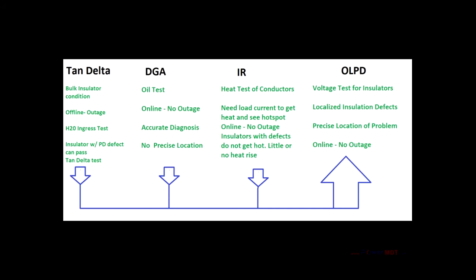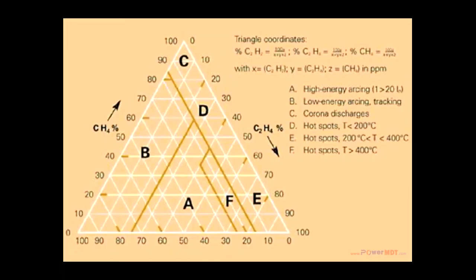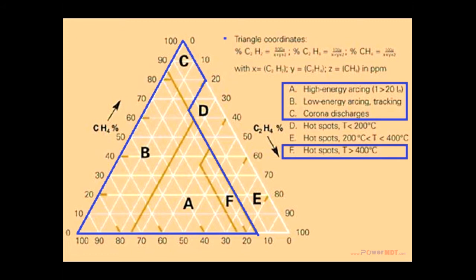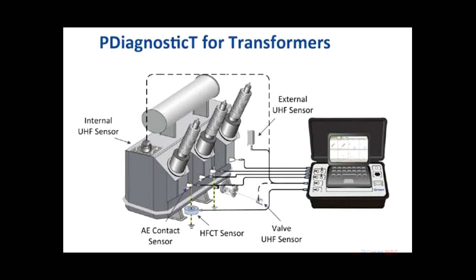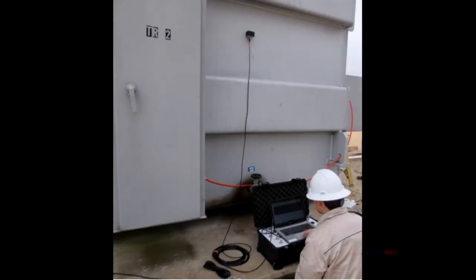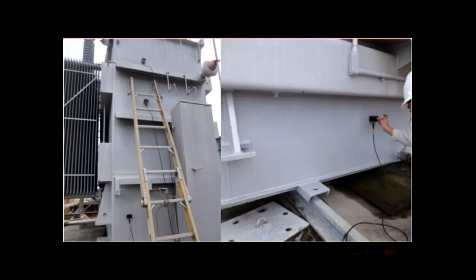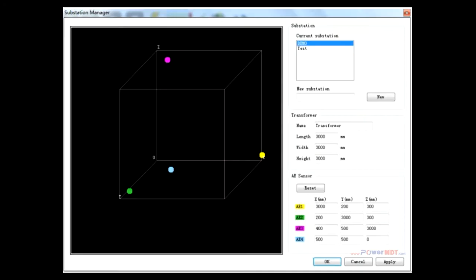These partial discharges can occur in various dielectric mediums such as oil, porcelain, resins, and polymers. DGA tests play a key role in identifying many issues in transformers and other oil-filled equipment. However, when acetylene and arcing gases are rising, the precise location of the issue remains unknown. In this situation, 3D acoustic triangulation can be used to determine the precise location of the discharge.